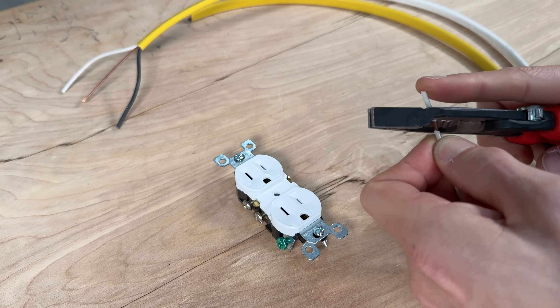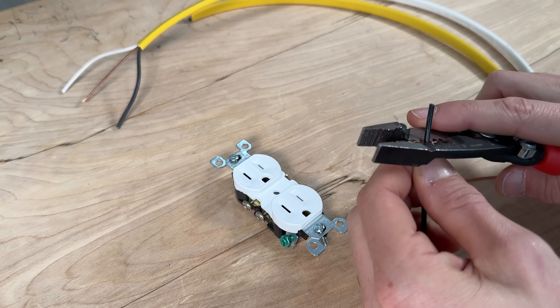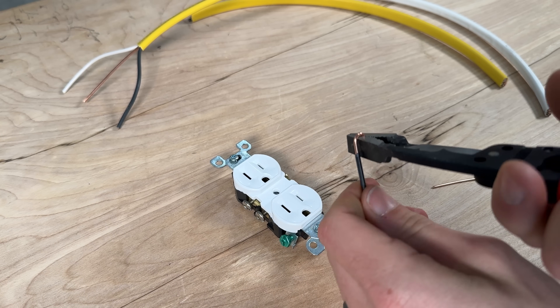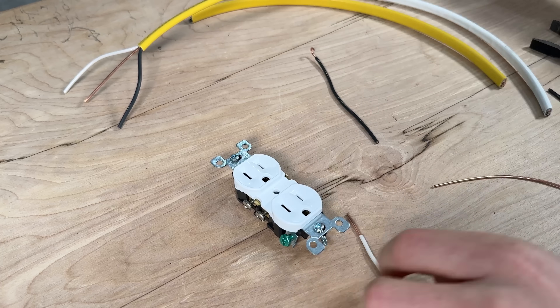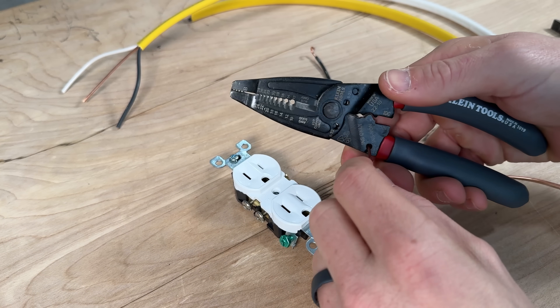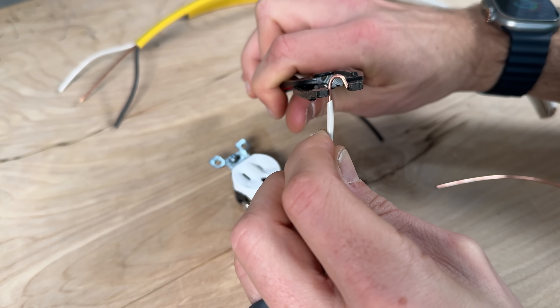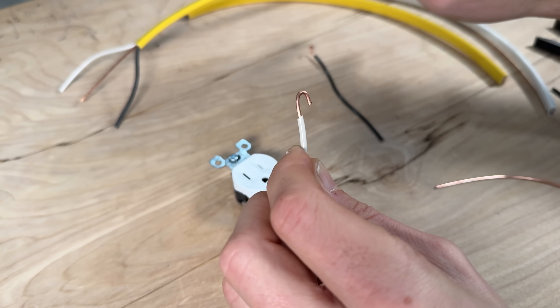You want to strip off about three-quarters of an inch of insulation from both your conductors. Then I'll use the jaws of my hybrid wire strippers by Klein Tools to make a perfect j-hook. If you have standard wire strippers you probably have a hole in the handle that can help you with a j-hook, and if it's a little open just crimp it down with your wire strippers to close off the opening.